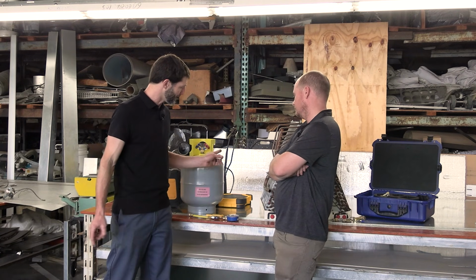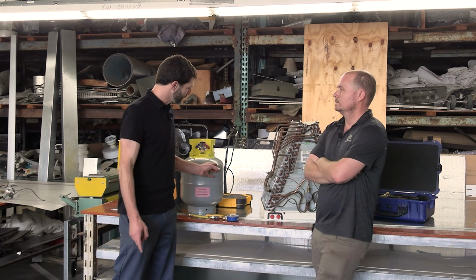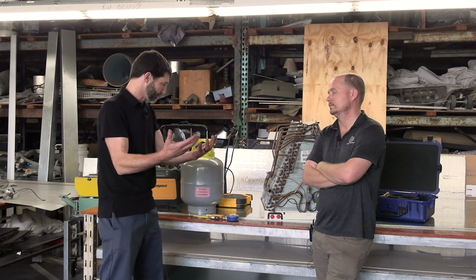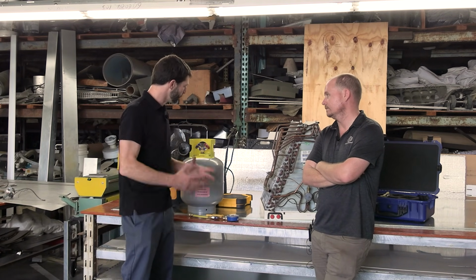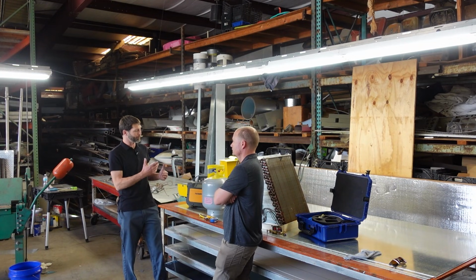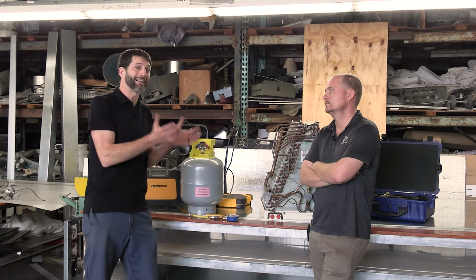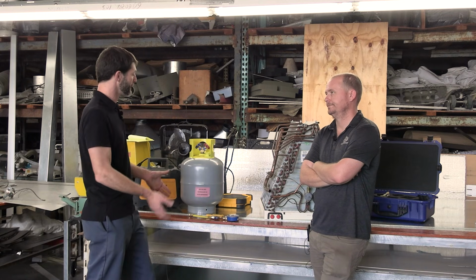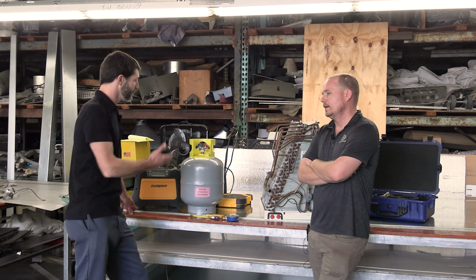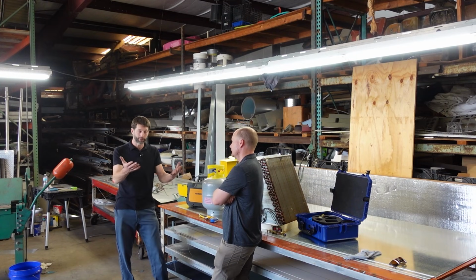And Brian makes a great point. I always recommend that your recovery bottle or even a virgin refrigerant bottle is on the scale the whole time. You're monitoring it, because just because the factory charge says one thing doesn't mean that's the actual amount of refrigerant that's going to be going into the tank, or into the system in the case of a virgin bottle.